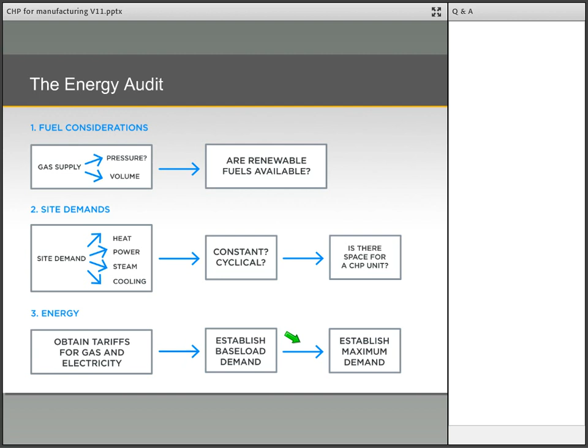But if in doubt, an undersized CHP will still save money, whereas an oversized unit will not. Could a CHP unit physically fit inside the boiler house or energy centre, or will it need to be placed outside in a container?